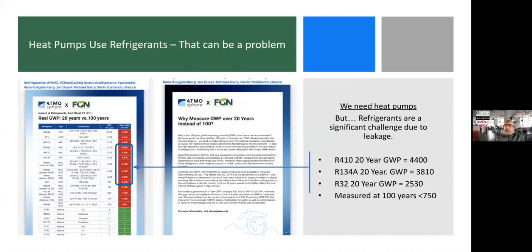And so the issue that we're facing through our electrification is, as we transition into electric heat pumps, we have to be mindful and maybe try to make the best choices on the refrigerant lines. Refrigerants are kind of complicated, and this slide was a learning event for me. One of my favorite refrigerants to replace the high global warming potential refrigerants in 410A and 134 was R32. It's a new synthetic refrigerant. It has a very low reported global warming potential of 750, which compares very favorably.